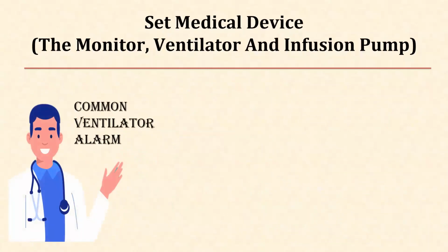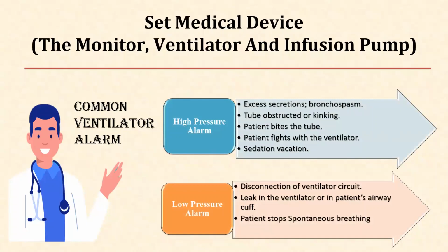There are some common ventilator alarms, such as the high pressure alarm and the low pressure alarm. A high pressure alarm can be seen in situations like if the patient has excess secretions or bronchospasm, or there is tube obstruction or kinking, if the patient bites the tube, if the patient fights with the ventilator, and when there is a sedation vacation. Low pressure alarms are seen in conditions like disconnection of the ventilator circuit, a leak in the ventilator or in the patient's airway cuff, and when the patient stops spontaneous breathing. So these are the causes for high pressure and low pressure alarms in the mechanical ventilator.